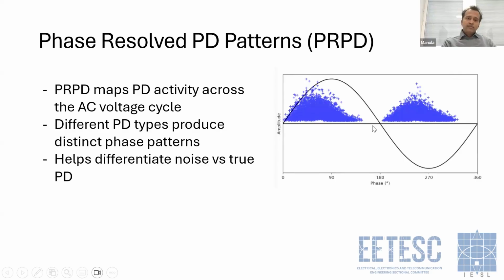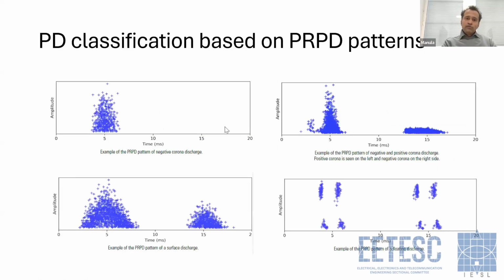These patterns help to differentiate or distinguish different partial discharges like corona discharges, surface discharges, internal discharges, or floating discharges. Here you can see how different PRPD patterns are correlated to different types of partial discharges. In this first picture, you can see the corona discharge, the negative corona. This cluster would appear only during the negative half cycle of the AC waveform. There is no cluster during the positive half cycle of the waveform, so we can easily categorize this kind of PRPD pattern as negative corona discharge.